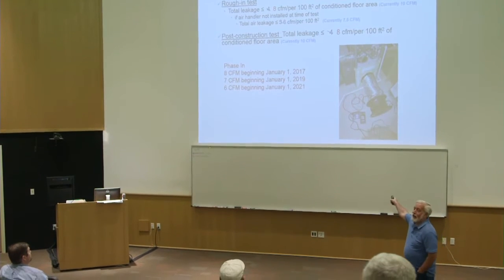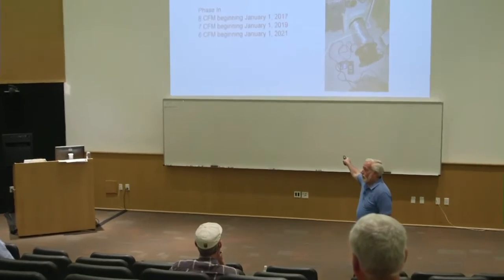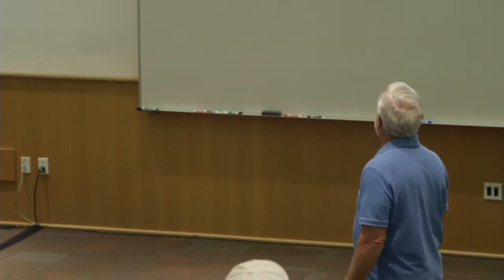Guess what? We don't have to do this if all your duct's inside the envelope. If you have 35% or more of your duct outside the envelope, you should be pressure testing it. And those of you that are inspectors should be requiring them to pressure test it. So if the air handler, furnace, or 35% of the duct is outside the envelope, you have to test your duct and ensure it doesn't leak.